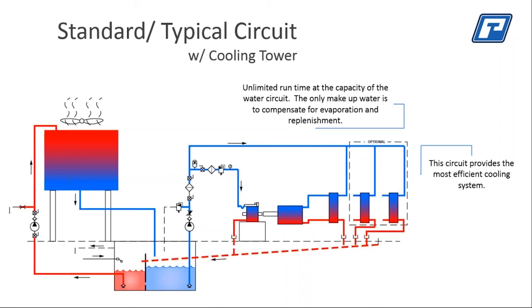Last question from Miguel, who has a great question. What is the percentage of water lost by evaporation on the tower? Oh, that's actually a very good question. Typically you can say that 2.5% of the water that's passing through the system is lost to evaporation.